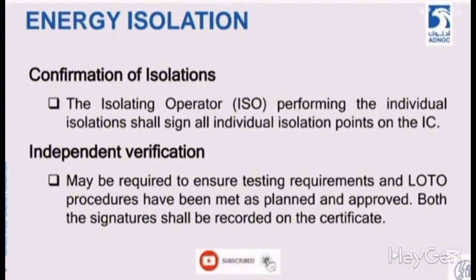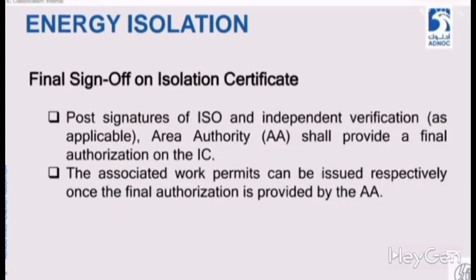So when your energy isolation independent verification is done, if LOTO was applicable and approved previously, it should also be applied. After that, both your PI and JP signatures must be on the isolation confirmation, which is the IC certificate, which we refer to as IC. For the isolation confirmation certificate, to be more authentic, the PI lock number and JP lock number must be mentioned on the IC. Final sign off on the isolation certificate.